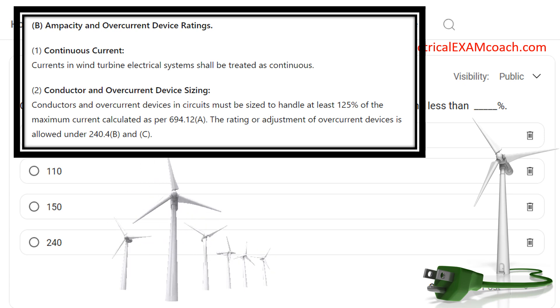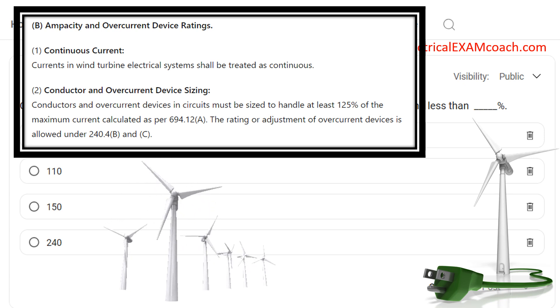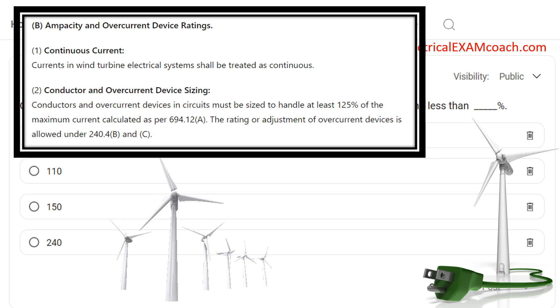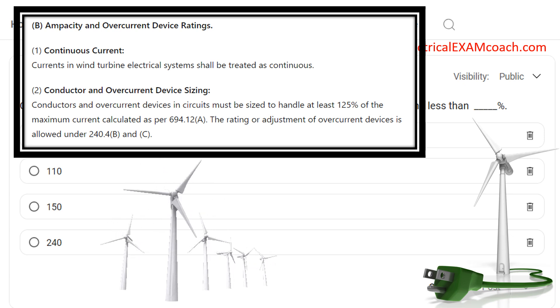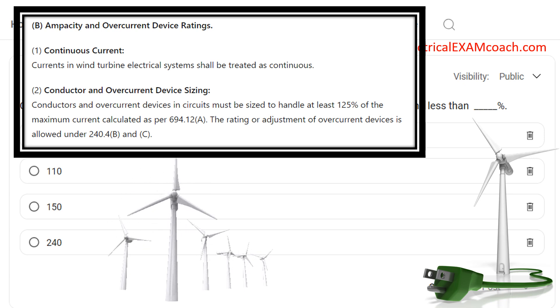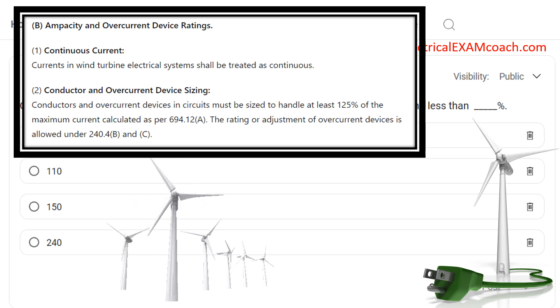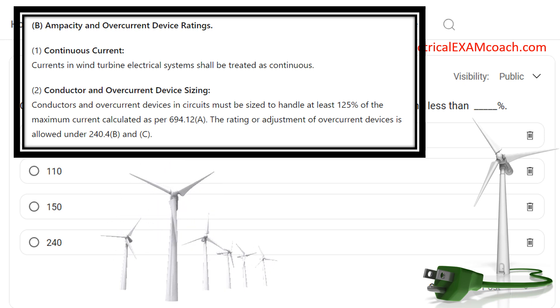It also says that the rating or adjustment of the overcurrent device is allowed under sections 240.4(B) and 240.4(C). What those sections allow us to do is, when it's 800 amps or less, protect the wire with a larger overcurrent device as long as we cover the known load. That's how we get our next size up rule.